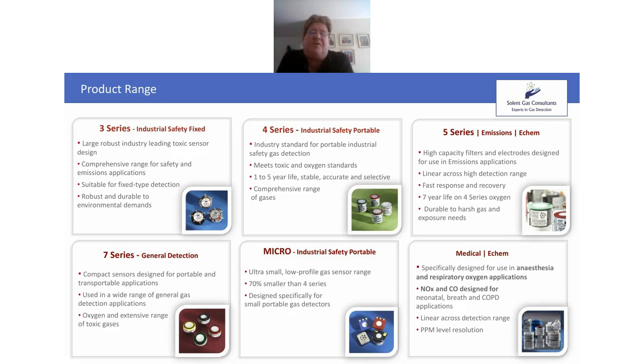So the next range was the 3 series sensor. These are quite big. They're still used fairly commonly. People like them because they're robust and tough and well tested. But they are quite big. The 4 series was a smaller version. The technology in terms of the operation of chemistry is much the same, but it's in a much smaller format. And these are very popular still today and used in a lot of the portable instruments. The 5 series is a larger sensor designed for use in emissions. So it's got a larger volume of electrolytes, larger electrodes.